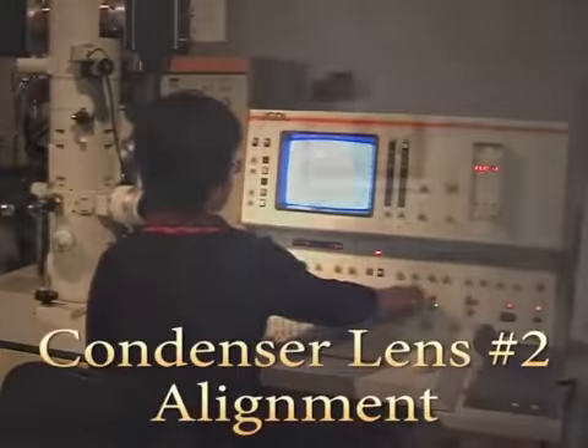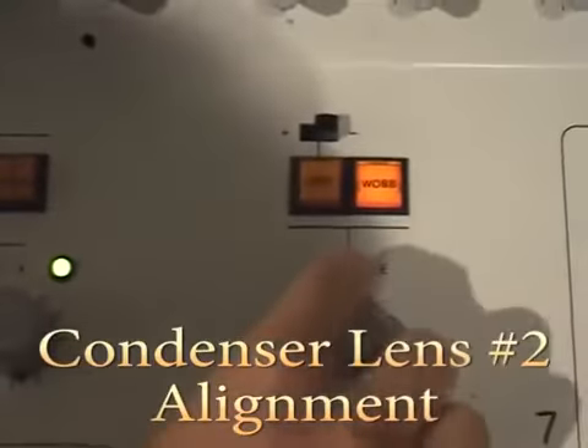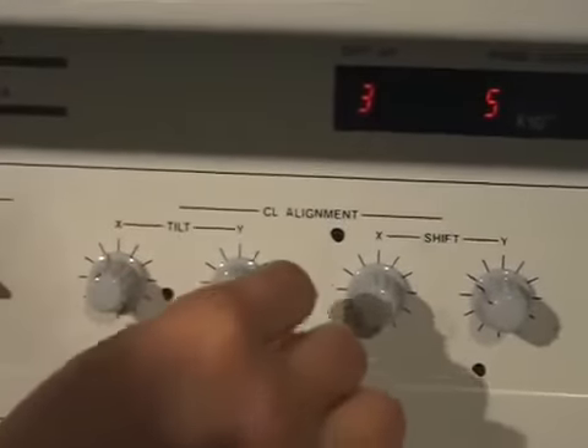Focus on a noticeable feature of your specimen. Press the wobbler button and adjust the amplitude so the image movement can be easily seen. Adjust CL alignment XY tilt knobs so that the image converges and diverges from the center of the screen but does not translate across the screen. Turn the wobbler button off.